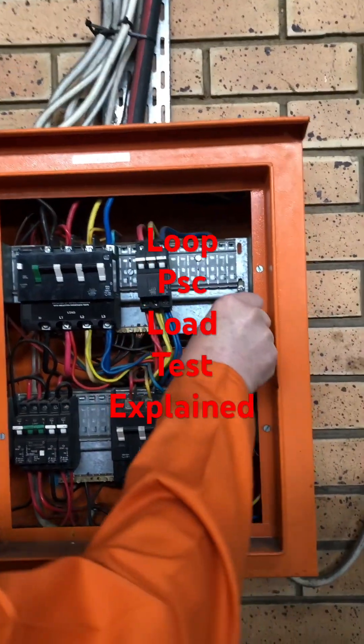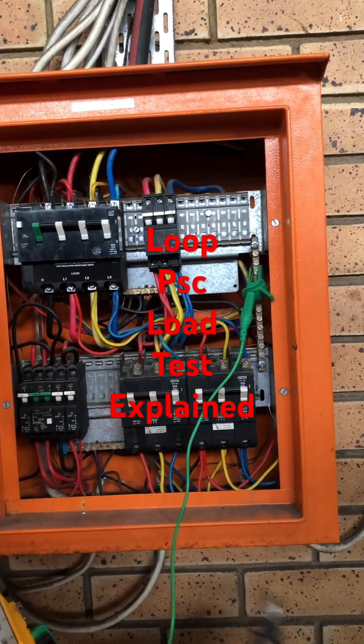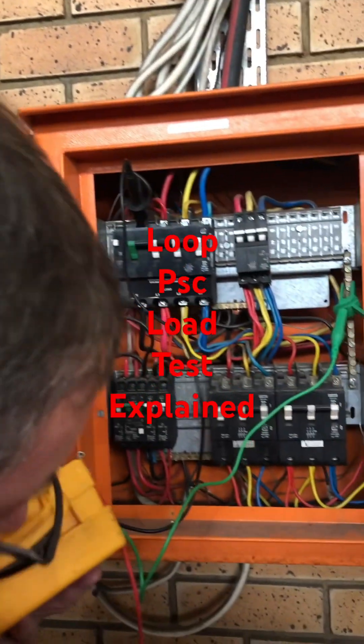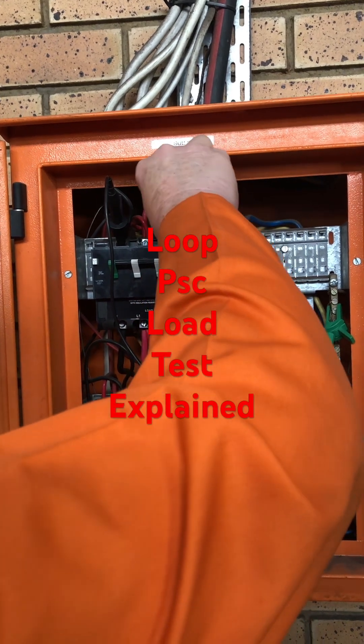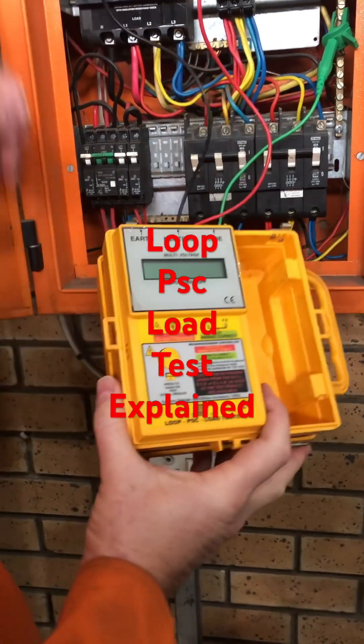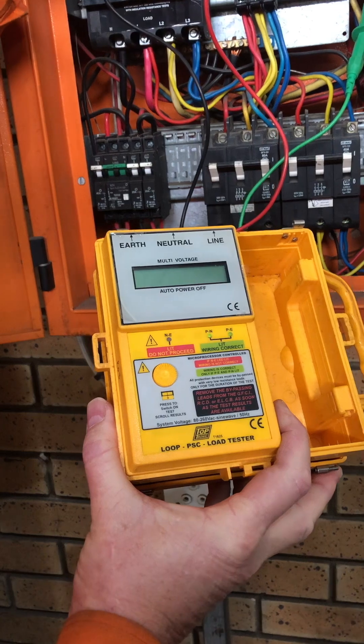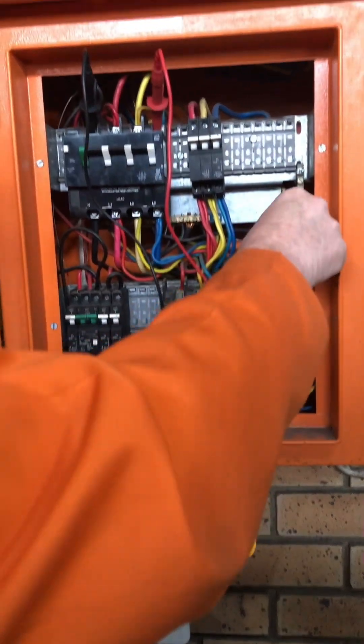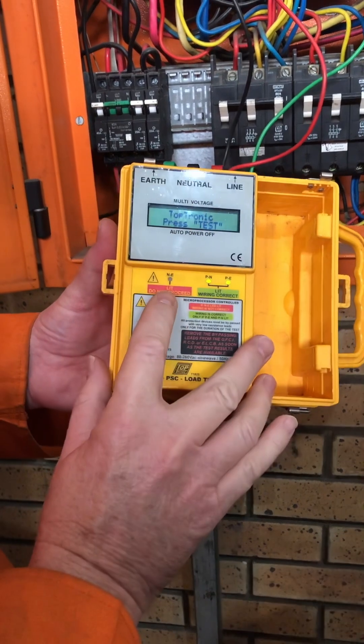So you put your earth, you put your neutral, and then you put your live. You can put your live on anyone that you can get to. You see there it's showing me it is correct. As soon as it's not connected correctly, you will get a red light which says do not proceed. Make sure they are quite tight, they won't just jump off. Then you press a button, switch on — now it says press test.